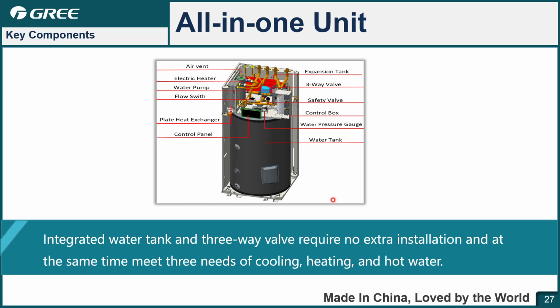Okay. Next one is the all-in-one unit. For the outdoor side, the outdoor units are the same as the split. However, the indoor unit is different because, just as I said, the hydro box and the water tank are integrated together. So you can see the lower part is the water tank, and the upper part is the hydro box, such as the control panel, plate heat exchanger, flow switch, water pump, e-heater, air release valve, expansion tank, 3-way valve, safety valve, electric box, water pressure gauge, and water tank. And finally, we use a metal cover to cover them.